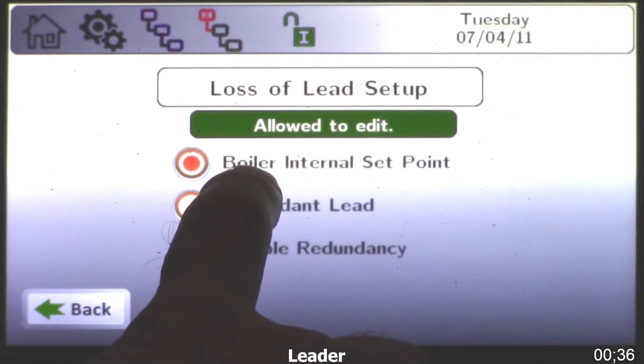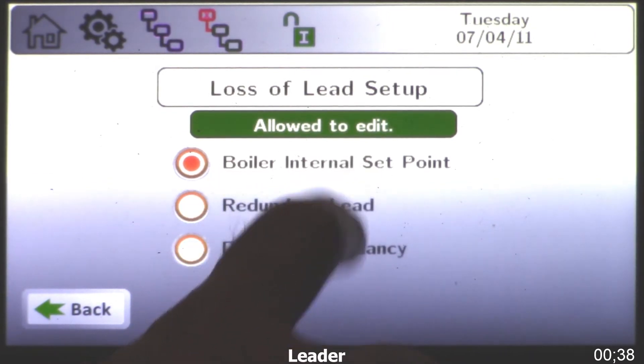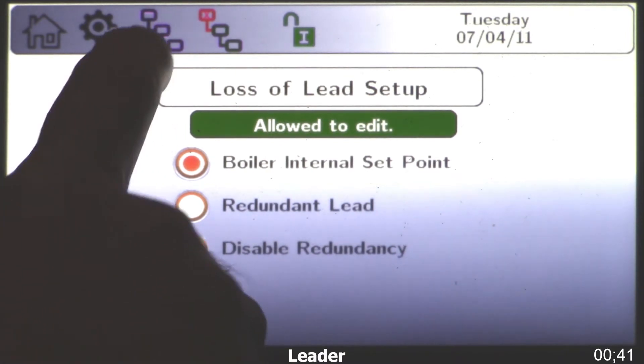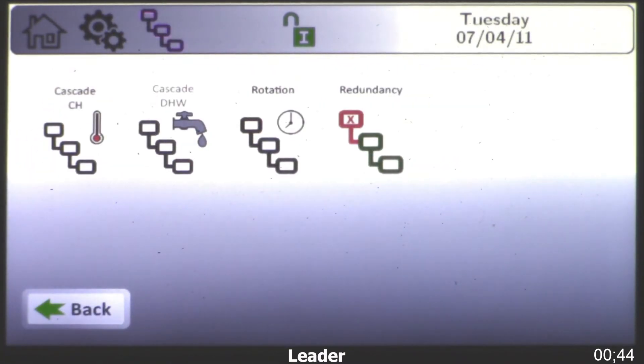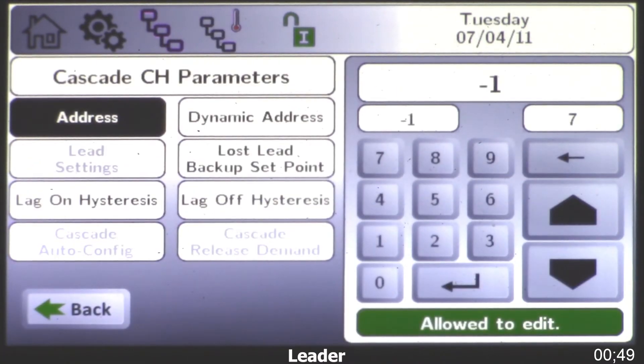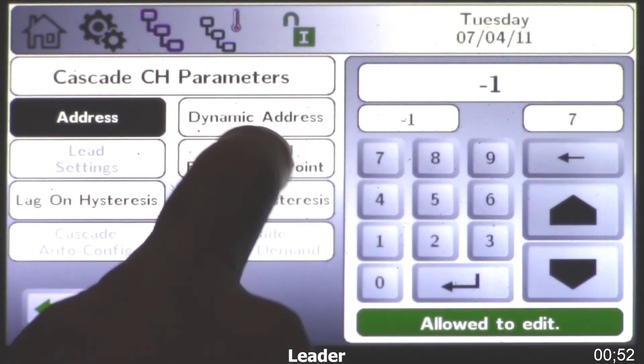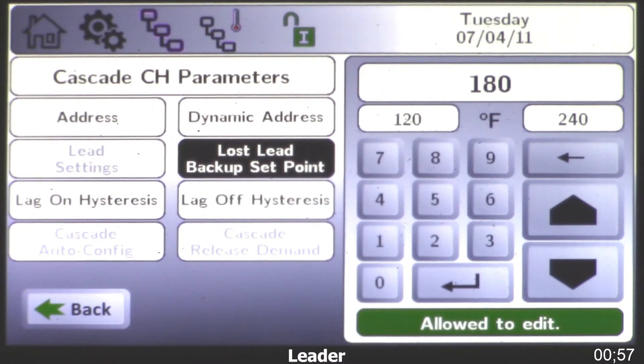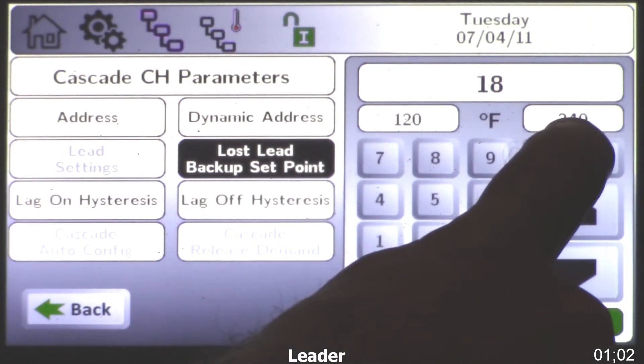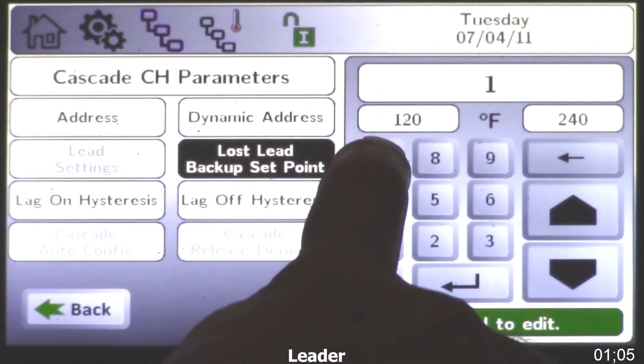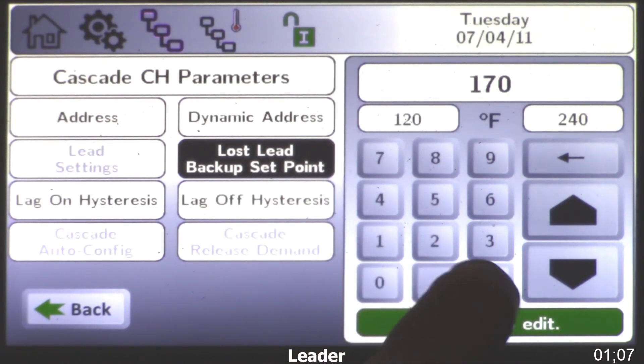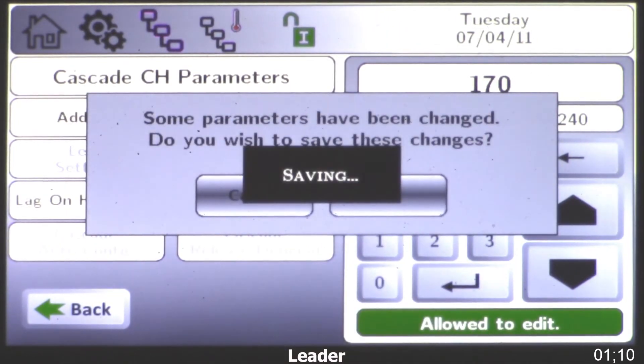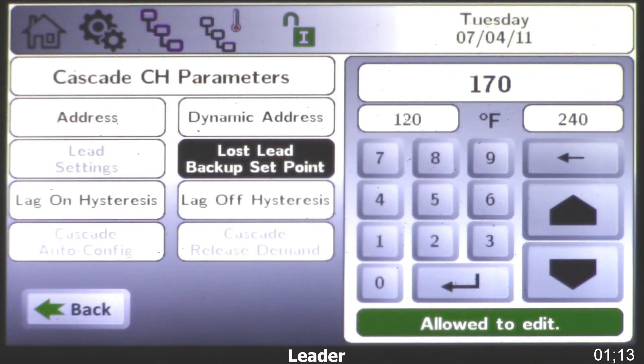It is already defaulted for boiler internal setpoint. I'm going to come back to cascade and choose cascade CH for this example. Now that lost lead backup setpoint — I'm going to click on this and give it a setpoint. This will have to be done not only on the lead boiler but the member or lag boilers as well. For our example I'm going to type in 170 and choose enter, then click OK.